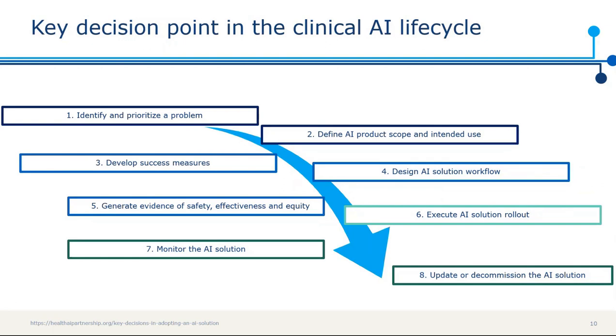And this is something that our team has struggled with a few times, is that it's actually pretty hard to have oversight of what the regulated menu is to pick from. So interrogating regulatory databases is really hard to see what the tools are. And what's even harder is to actually see what intended use statement they're regulated against, to actually get nailed down what is within scope of use and what is not, because there's a big risk that users can start to use tools for things that they're not really meant to be used for.